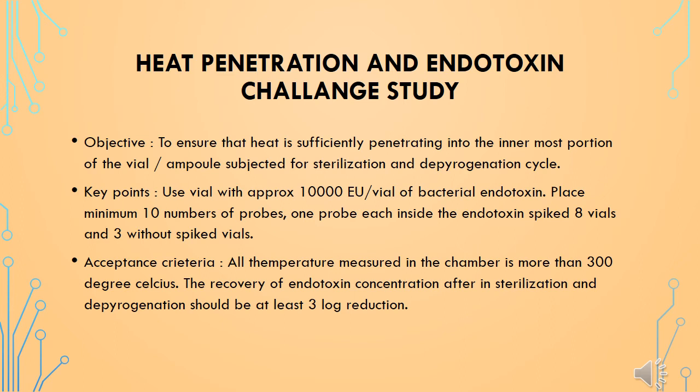The fifth and very important test for qualifying the depyrogenation tunnel is heat penetration and endotoxin challenge study. In this test, 9 to 10 spiked vials with approximately 10,000 EU per vial of bacterial endotoxin from microbiology are used. The objective of this test is to ensure that heat is sufficiently penetrating into the innermost portion of the vial subjected for sterilization or depyrogenation, to achieve the desired temperature during the sterilizing or depyrogenation cycle.